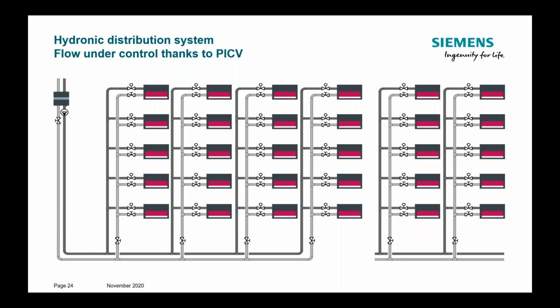So this we have seen from Luca, a nice wide hydraulic network with a lot of consumers. Thanks to the PICVs, we now have the flow under control. We can avoid starving coils, we can avoid excessive overflows to consumers, and we have also optimized the needed energy for the pump. But have we really done everything to guarantee energy efficiency in this system? And have we done everything to guarantee a good and optimized power distribution to each and any consumer? Can we at least guarantee that each riser gets the right power? Can we optimize the operational costs on these?